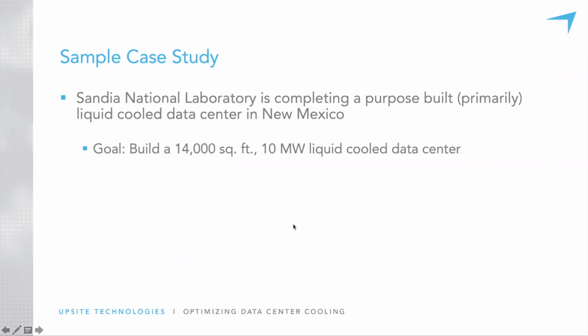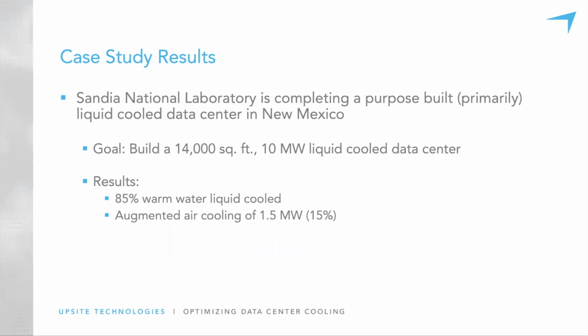So a number of you might have read a white paper. You guessed quite well. The results are that they came to the conclusion that they would be able to use liquid for 85% of the cooling, and that they would need to augment that with 15%, or 1.5 megawatts, of air cooling. So they have a few perimeter cooling units around the room to pick up that heat that is either given off by components that just can't be put in liquid, don't have a liquid-cooled solution, or that the liquid solution doesn't pick up. So well done. Glad you participated in that, and a lot of you got that right.